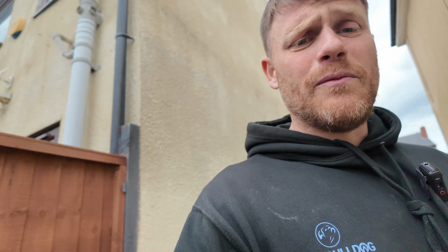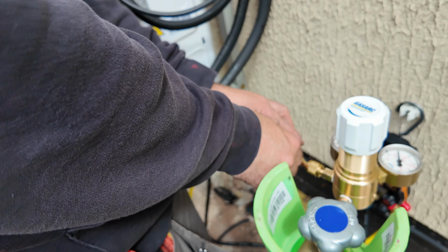So we're going to put that down to 44 bar. Now it depends on what system you're fitting - let's say we've got the Bosch unit here, that's what it says in the Bosch unit, 44, 48. You've got to check the manufacturer's instructions, don't just assume it's 44 and 48 on any type of system you're fitting. It's not going to be - it'll be different for each type of system you're installing. So let's get back down to 44 for the pressure test.